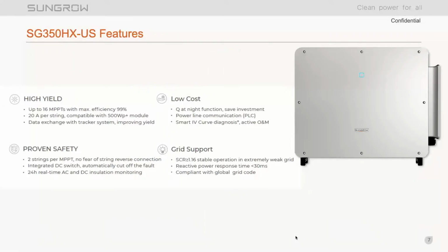So a quick introduction to the SG350HX. Just taking some highlights from the data sheet here. We're going to have basically two different flavors of inverter to offer the market, but the standard offering is going to have 16 MPPTs with a max efficiency of 99%. In order to meet the demands of the high power modules that we're seeing start to penetrate the market, we're going to be offering 20 amp per string maximum current tolerance to be able to get your DC to AC ratio in that sweet spot where you want to see it for those high power 182 and 210 millimeter modules that are coming out.